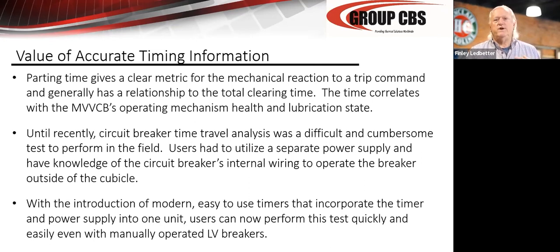There are also vibration techniques with our circuit breaker analyzer. Other people have vibration analysis equipment that will give you the mechanical condition of the breaker. But really the timer is your proof test. If the breaker is operating to speed, and believe it or not, if it sounds right, I would say that you have a healthy mechanism, you have a healthy breaker. So speed and velocity, or at least speed and parting time, is your best indicator of the mechanical condition of your breaker. Obviously, nothing will ever replace a set of eyes and a good visual inspection.